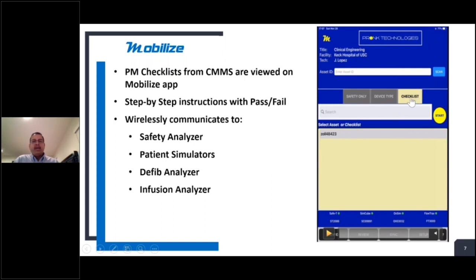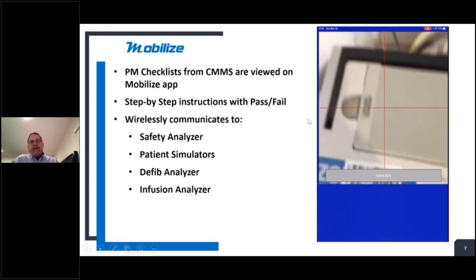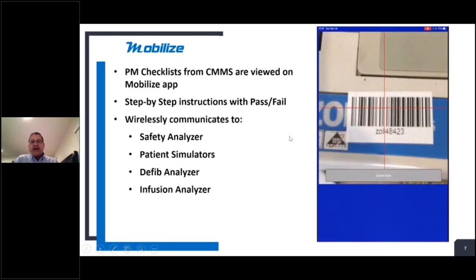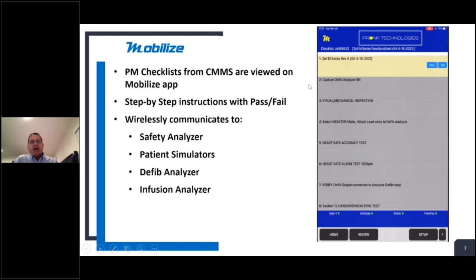You can see here the application has 3 different modes you can use it in. What we call checklist mode, which is the step-by-step procedures generally driven from the CMMS system. You have what we call device type, which are the onboard testing protocols you can create and customize. Or if you're just doing a basic safety inspection and you only want to do safety testing, you can use it in that mode as well. So the idea is to go up to the medical device you're going to use. If you have a barcode scanner, scan that barcode of the device. It's going to save that on there, and it's going to automatically open up the procedure for that device.